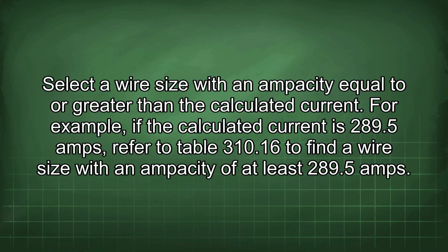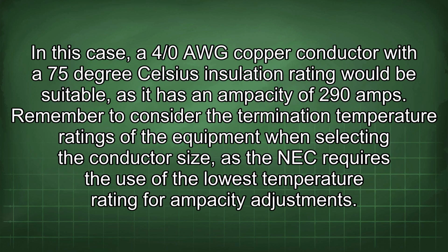Select a wire size with an ampacity equal to or greater than the calculated current. For example, if the calculated current is 289.5 amps, refer to Table 310.16 to find a wire size with an ampacity of at least 289.5 amps. In this case, a 4/0 AWG copper conductor with a 75 degrees Celsius insulation rating would be suitable, as it has an ampacity of 290 amps.